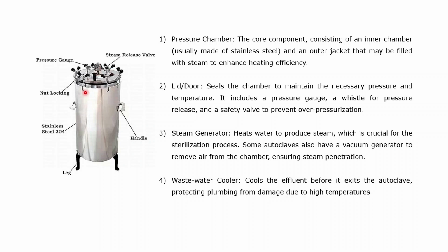So you are basically sealing it up, and after sealing it up you are switching it on, and once it's switched on, there is a steam generator there, right? As I said, there is water inside the autoclave. Once the steam generator is on, it starts to make steam out of the water, and this steam in turn produces the pressure because it is a sealed environment within that autoclave. The steam elevates the temperature, and also it produces pressure within the autoclave, and this leads to the sterilization process there.